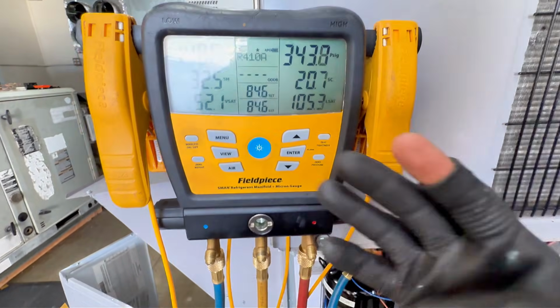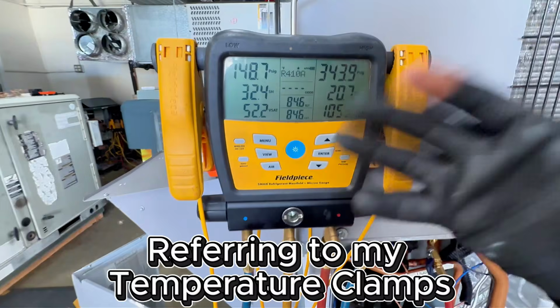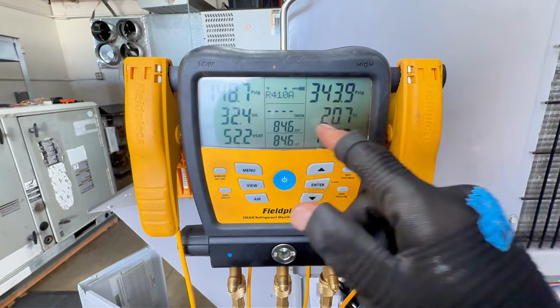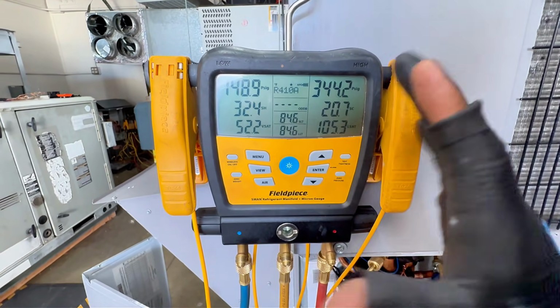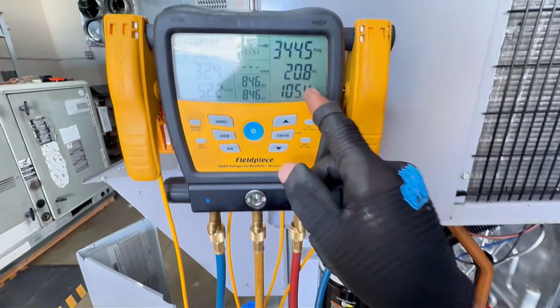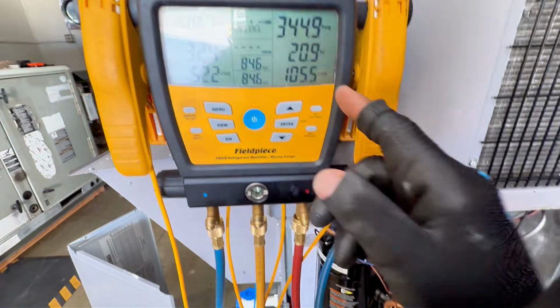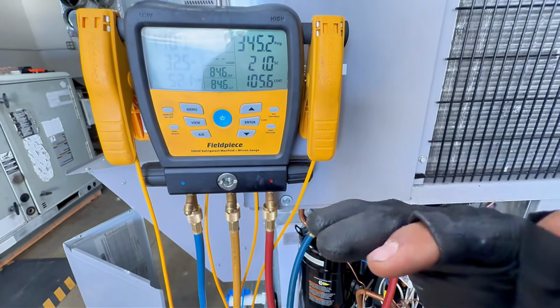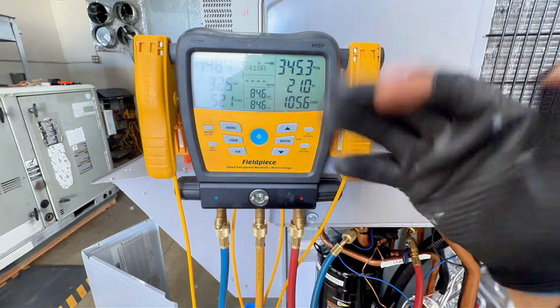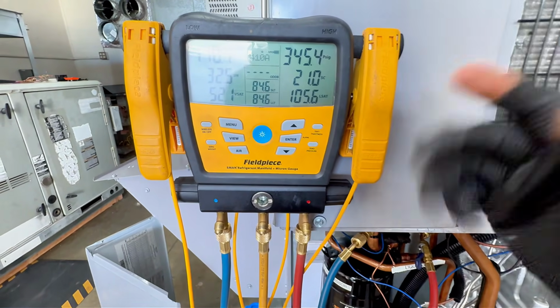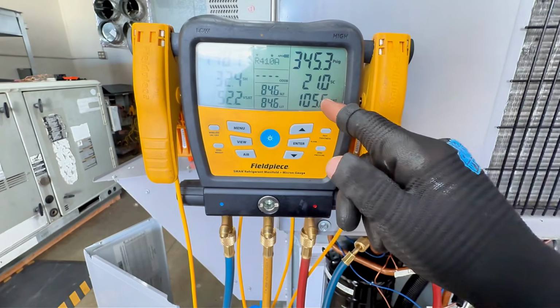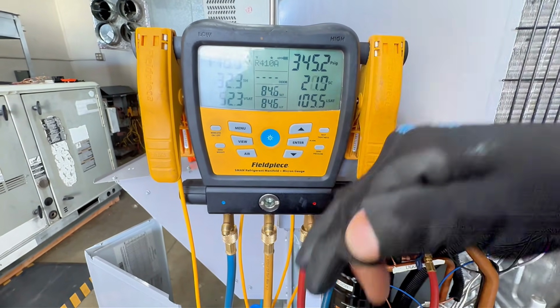Let's say your subcool, and keep in mind I have nothing connected, this is just your imagination, but let's say your subcool is 20 when it should be around 8 to 12. You're over 12 degrees on subcool. That compressor is going to be pulling a lot more amps, more energy for no reason. So you would have to recover, and you'll see your amps go down.